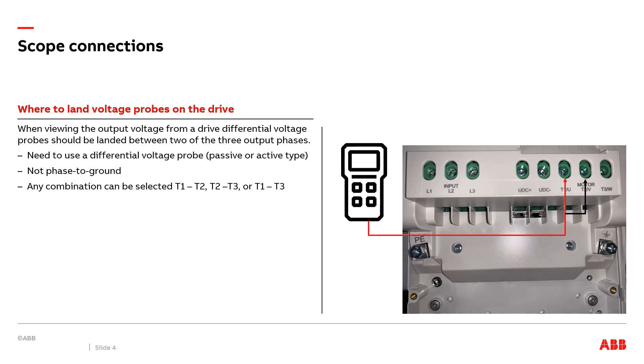In the picture on the right, I'm showing the scope hooked up to terminals near the VFD. However, if you're concerned about peak voltage or rise time potentially damaging a motor and you're troubleshooting a motor issue, it may be best to hook up the scope as close to the motor as possible. In that scenario, you may need to open up the motor conduit box. So the picture shown would actually represent making connections at the motor, not at the drive.